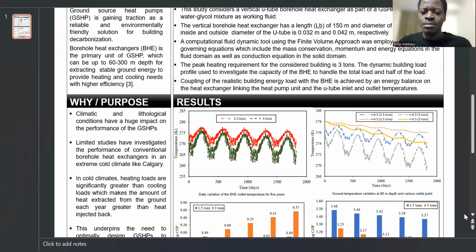So looking at the bore outlet temperature, it is important to mention that the outlet temperature of the ground heat exchanger is the inlet into the heat pump, and it's very critical in determining the operation of the heat pump, because most heat pump manufacturers will specify the threshold of the minimum entering water temperature into the heat pump. So the heat pump considered in this case has a minimum temperature requirement of 267 Kelvin, which is equivalent to -6 degrees C.